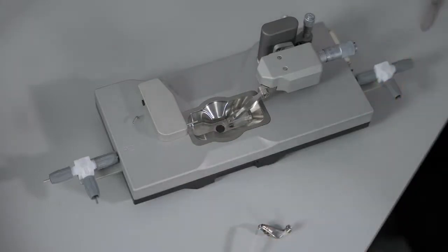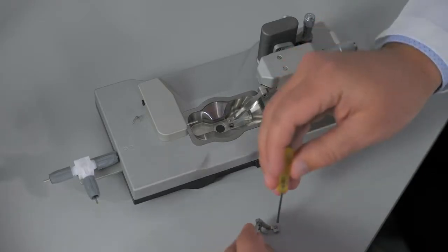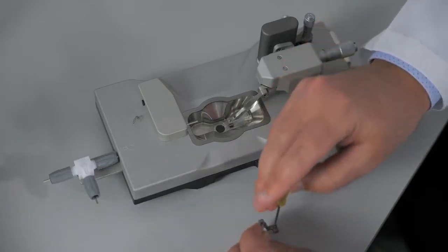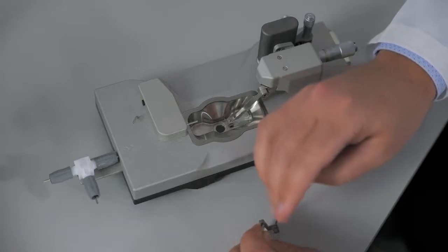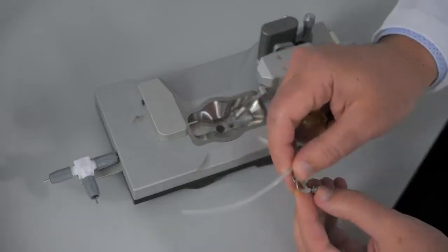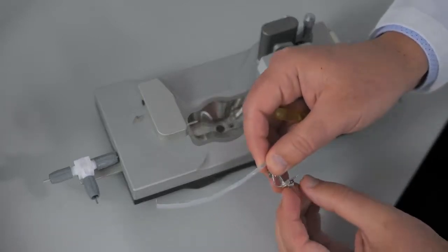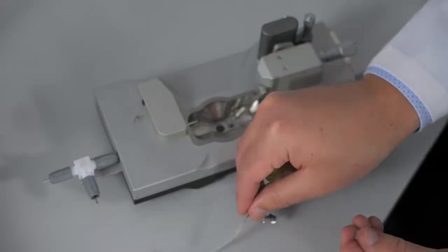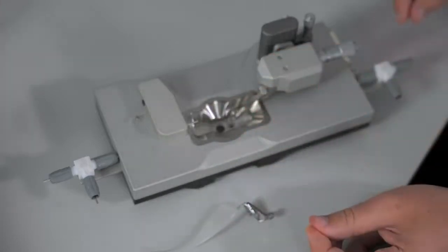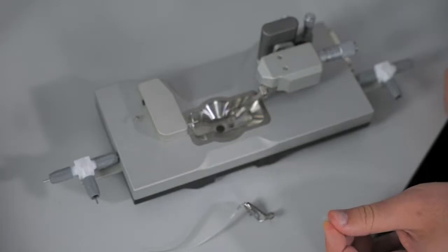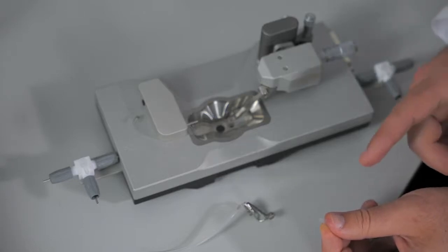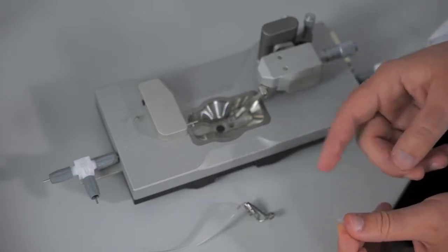Then you will do the exact same protocol as you did on the right side, where you release the plate that holds the cannula and then remove the tubing from the mount. Now you will cut another cannula to match this length and place it back in the tubing. Then you will reassemble the tubing and the cannula back on the mount.